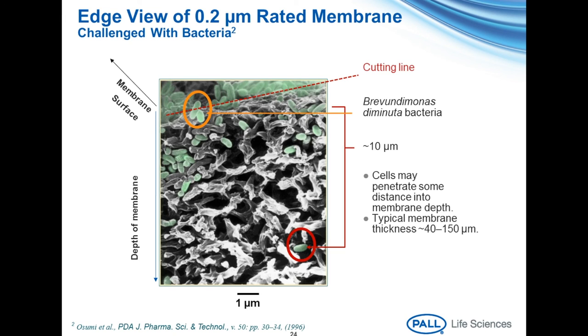A typical membrane thickness is roughly 40 to 150 micron. The thickness of the membranes, along with using a multi-layered approach, is critical to bacterial retention, especially with a high-risk fluid.